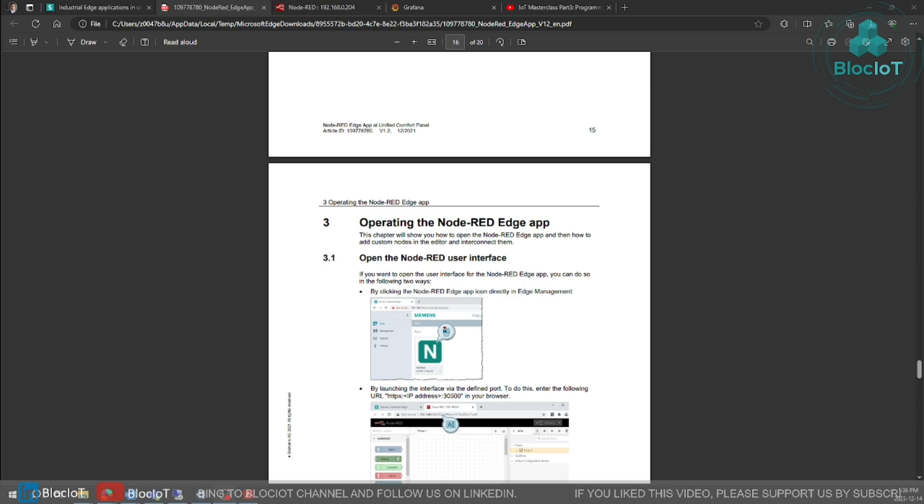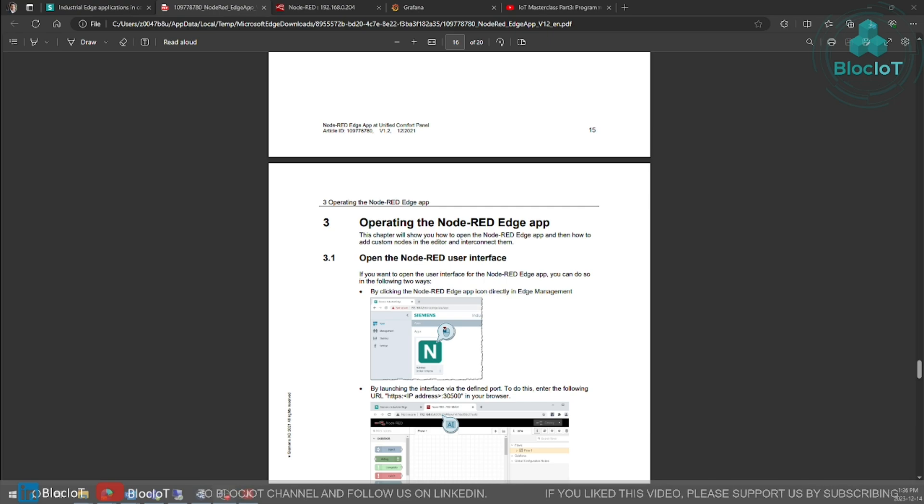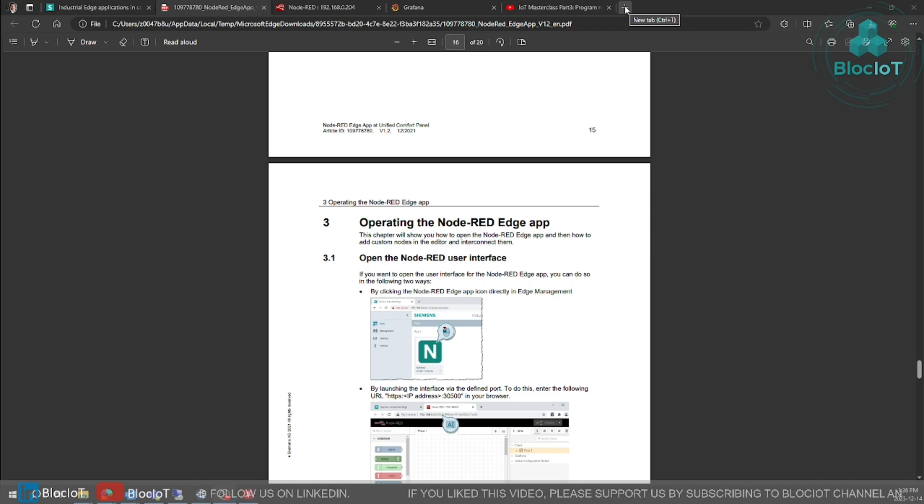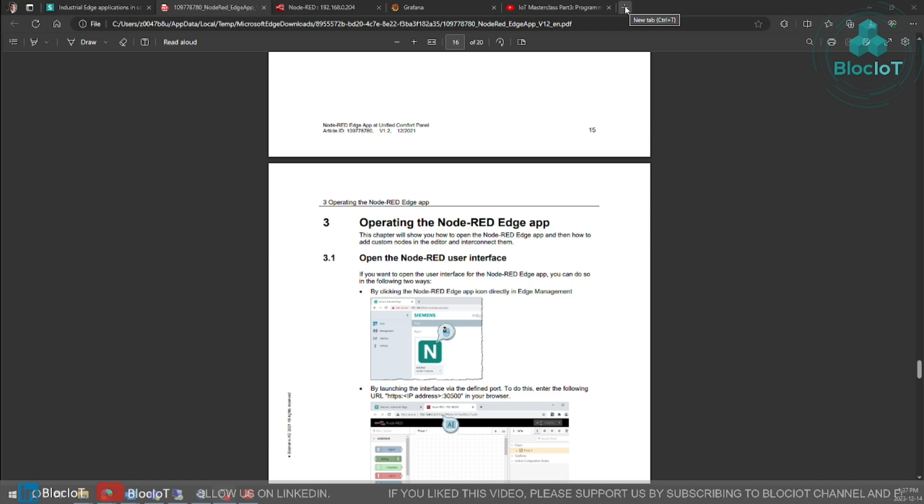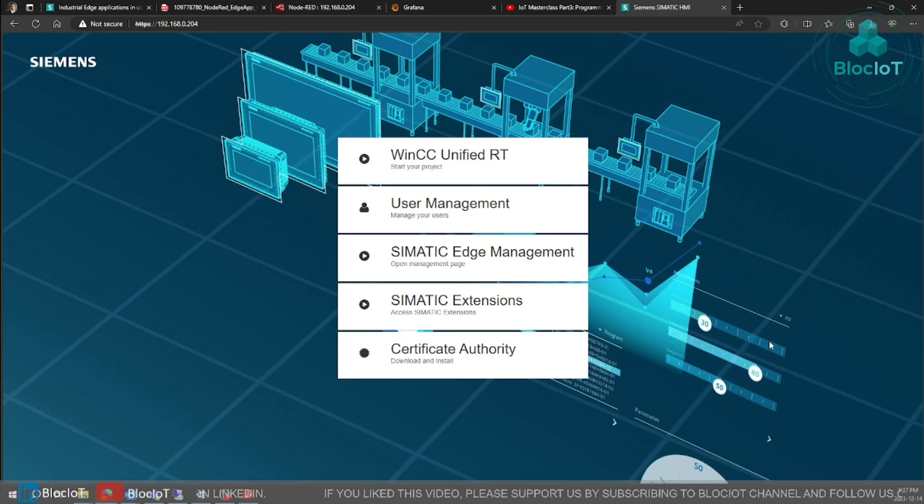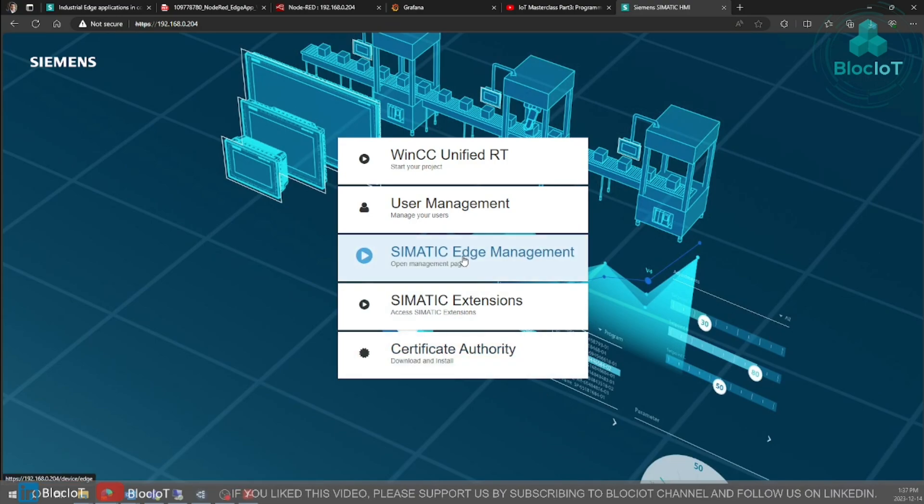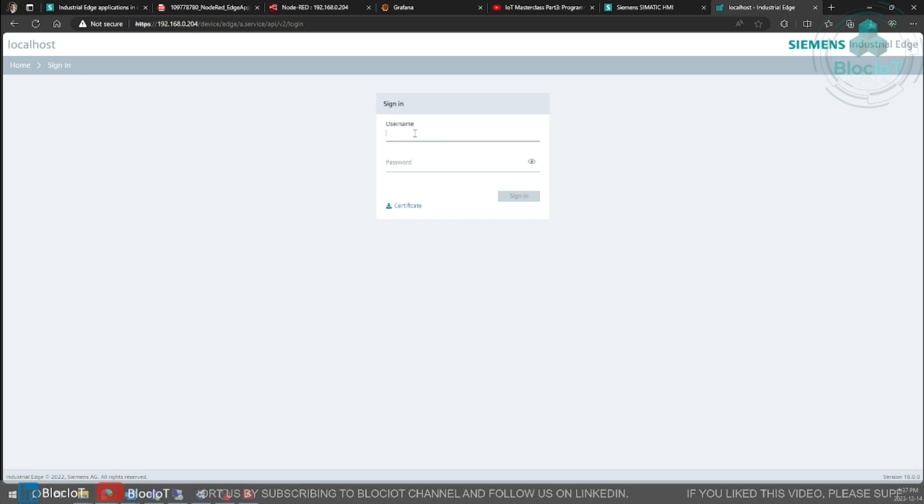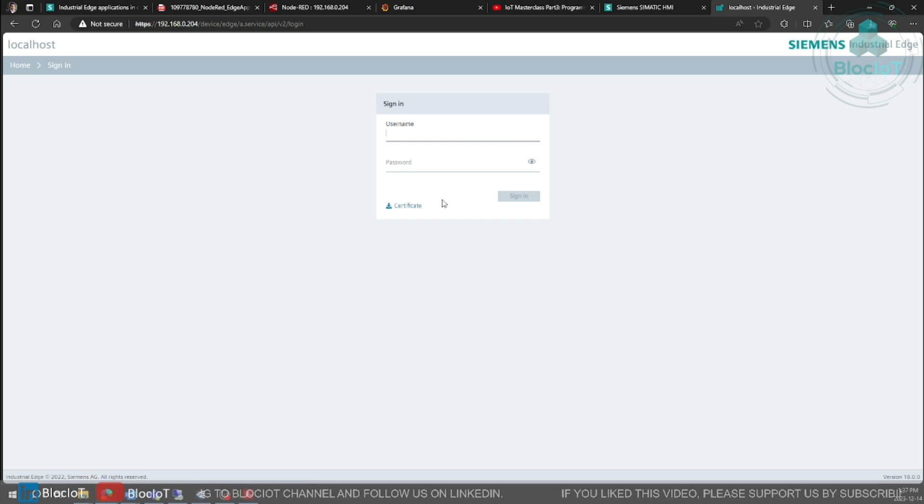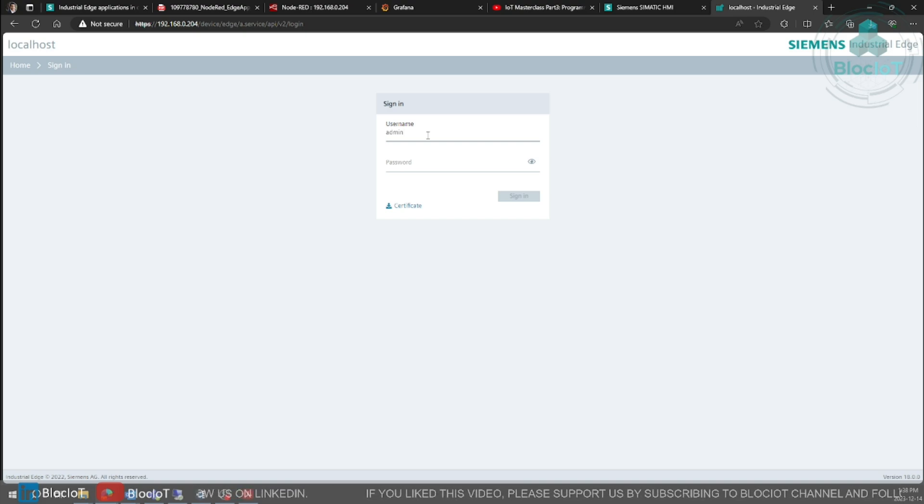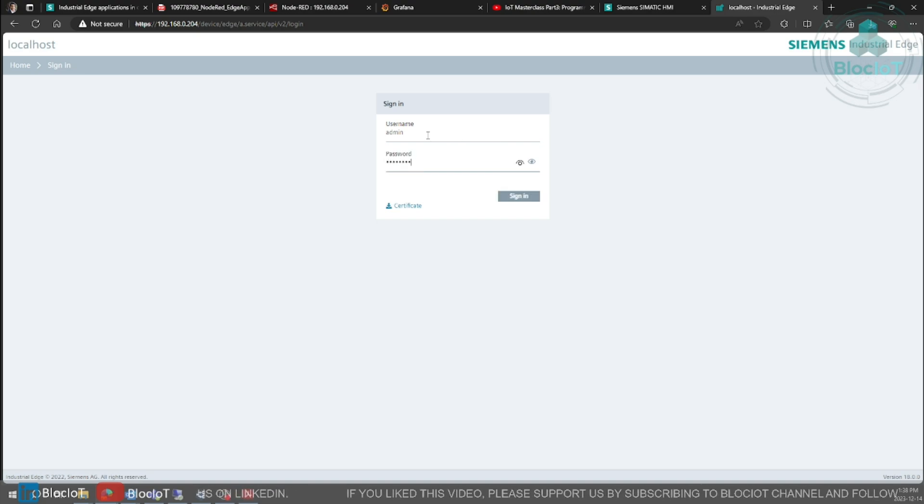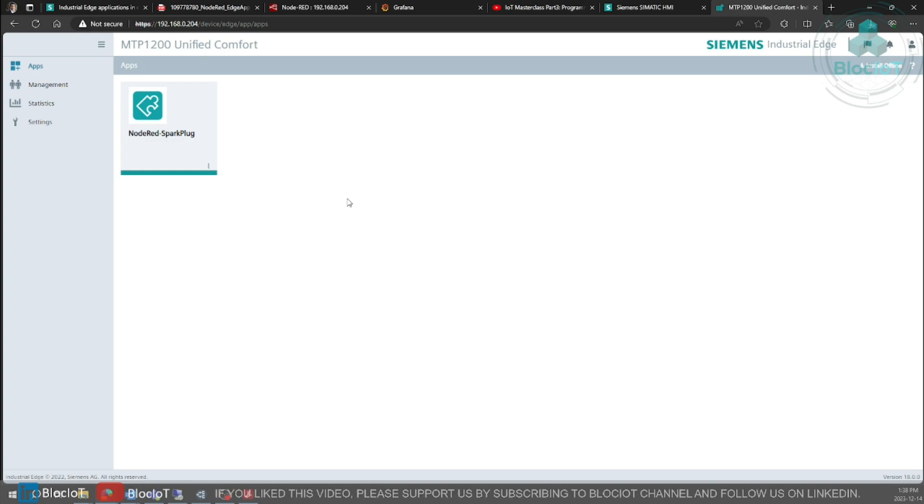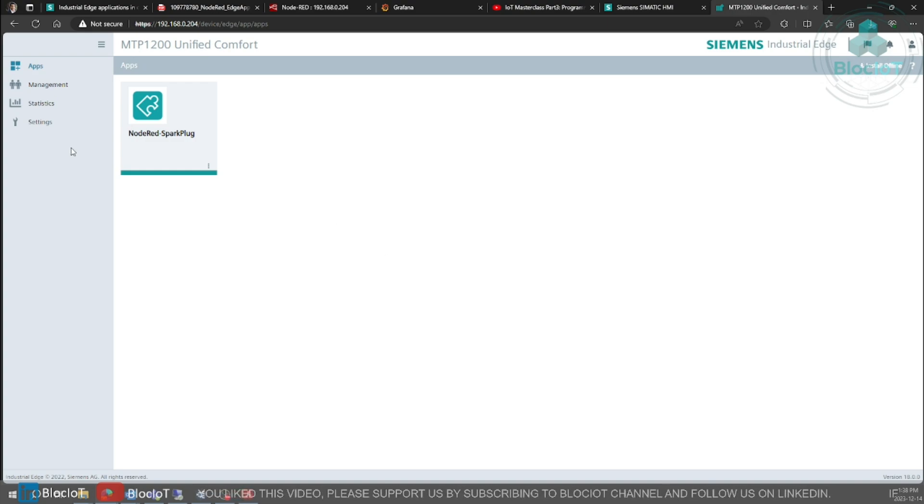So now the Simatic Edge app is enabled on our comfort panel. To access your edge management console, just simply type in the IP address of your HMI panel in a browser. And you need to select Simatic Edge management. You need to enter your credential to log in. This username and password can be defined in TIA portal when you create HMI project.